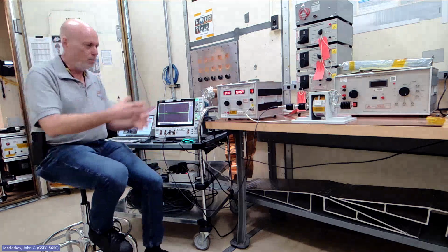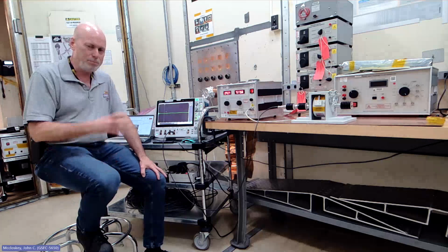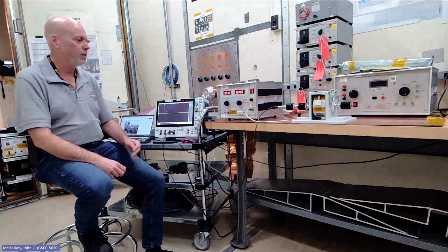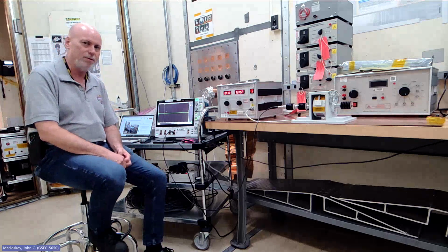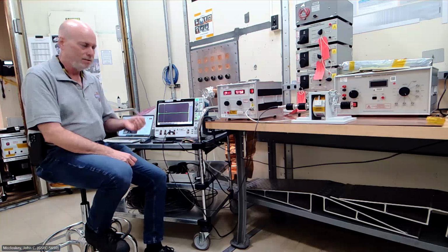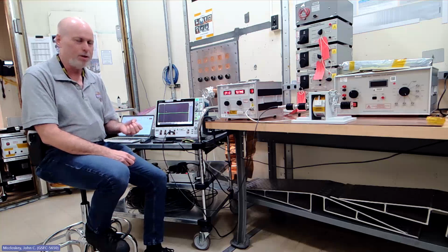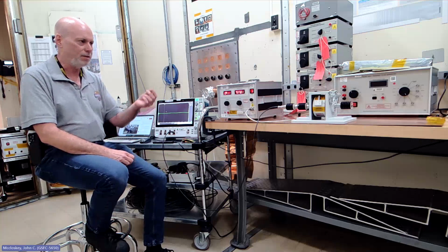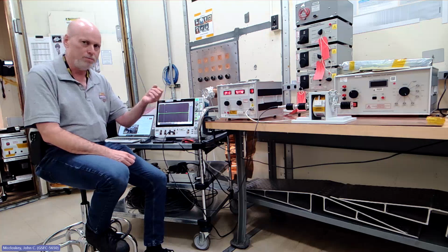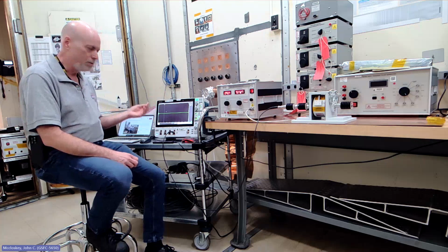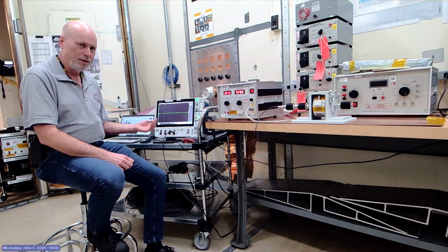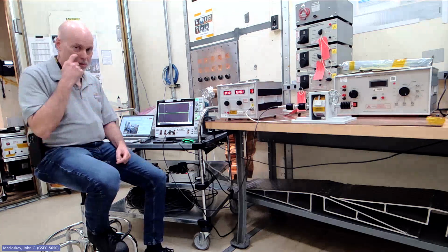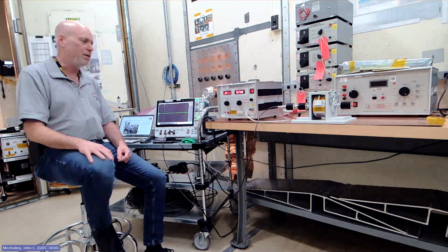So to review, we'll repeat the pre-calibration step just to get anchored, right? Know what the signal characteristics are that we're injecting. This all underscores the importance of the pre-calibration step. You want to inject into a controlled setup, a controlled impedance, so you know what it is you're injecting, because it is going to change once you inject into a real cable under test.